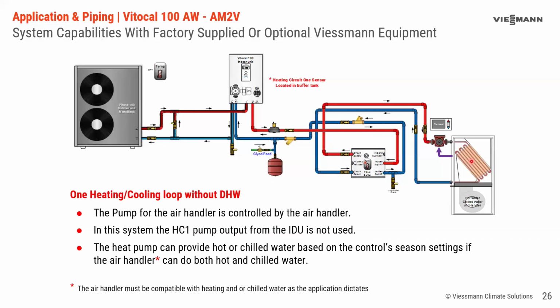So you make sure your air handler is suitable for hot water and chilled water, or the option would be to put a chilled water box coil in the top with its own control logic and potentially its own circulator. So it's much simpler if you just pick the right air handler off the bat. Viessmann currently is in development of an air handler like that. The air handlers we are selling in North America are hot water only. So this would be something that would be coming in the future from us. But just to be aware of that, the air handler, if you're going to use this for hot water, chilled water, the air handler has to be suitable for that.